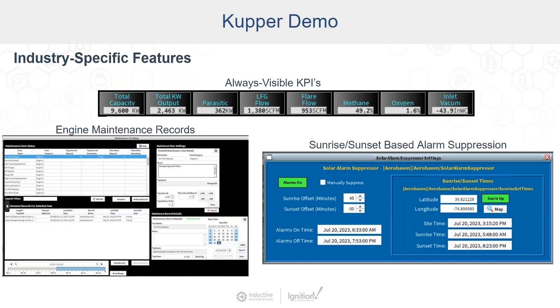On the bottom left, we developed a maintenance interval tracking system, which allows the operators to create grouped maintenance items, which can alert on a tag data-based interval, such as engine run hours, or a calendar time elapsed, or both. This generates reports for maintenance records as well.